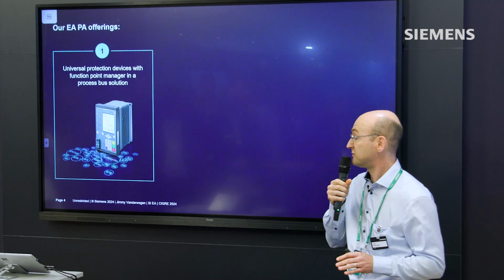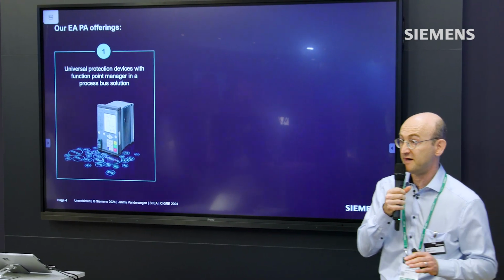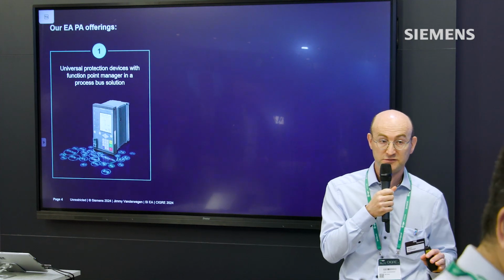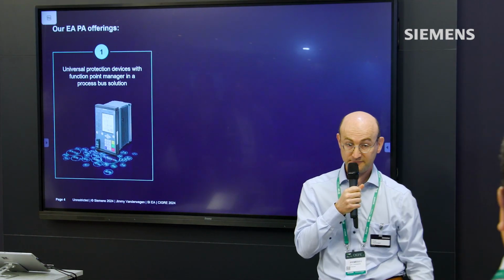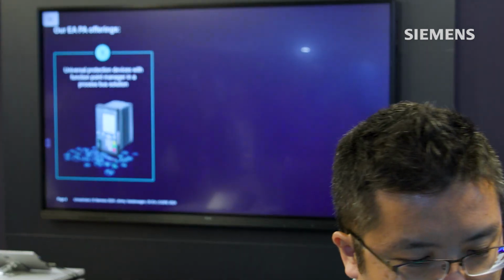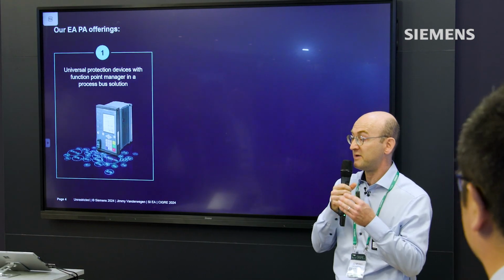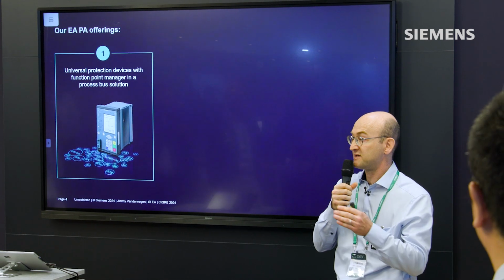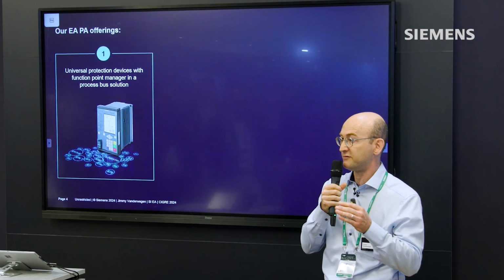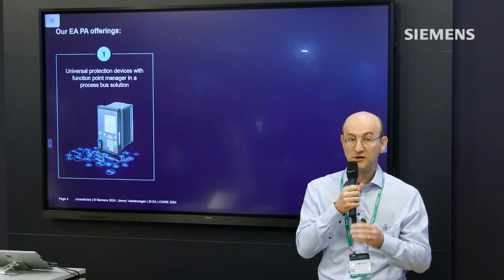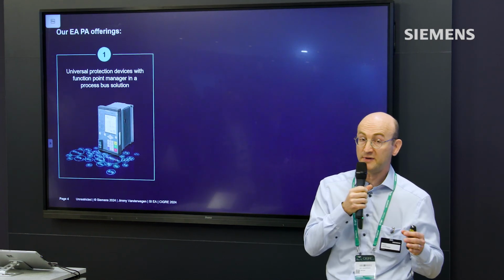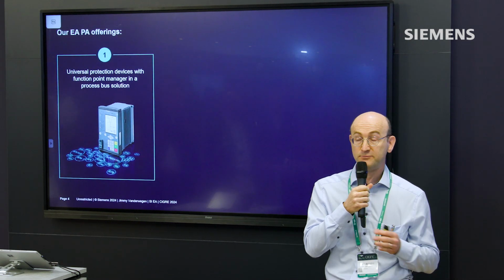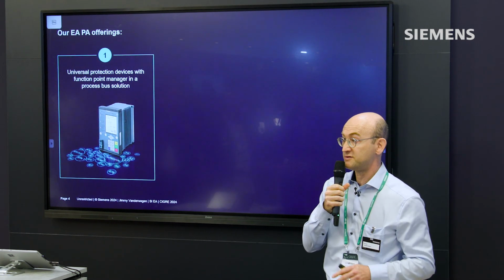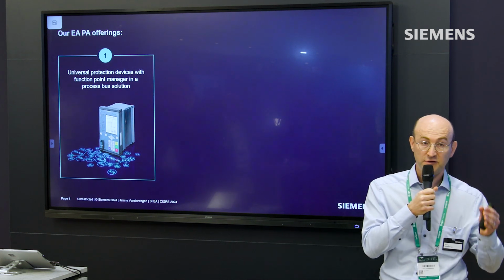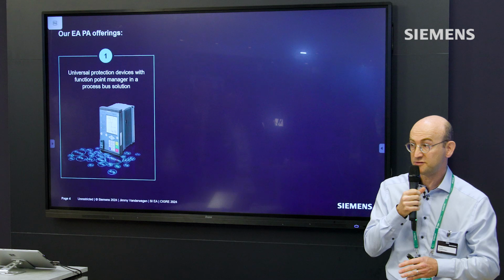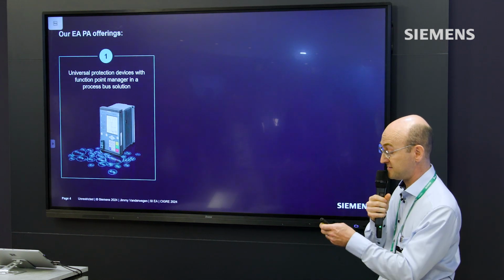The first solution is our universal protection device with function point manager in a process bus solution, which you can see over there. With the universal protection relay, you can buy the hardware for all kinds of protection applications together with an amount of function points. You install it in panels, and when the software team is ready with the configuration, you put the right configuration in the relay by changing the function points into protection applications. This way, you win time in project realization.